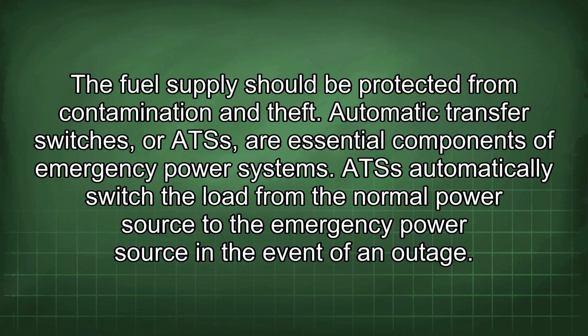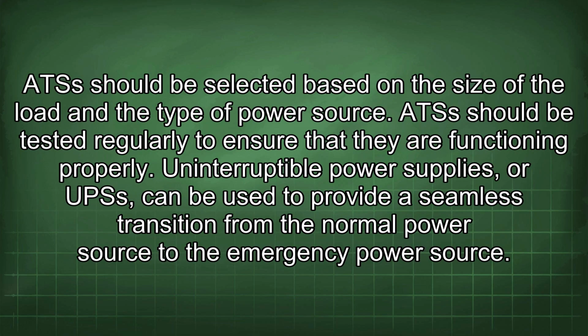Automatic transfer switches, or ATSs, are essential components of emergency power systems. ATSs automatically switch the load from the normal power source to the emergency power source in the event of an outage. ATSs should be selected based on the size of the load and the type of power source. ATSs should be tested regularly to ensure that they are functioning properly. Uninterruptible power supplies, or UPSs, can be used to provide a seamless transition from the normal power source to the emergency power source.